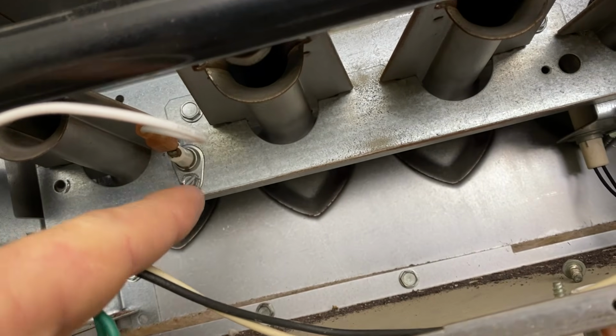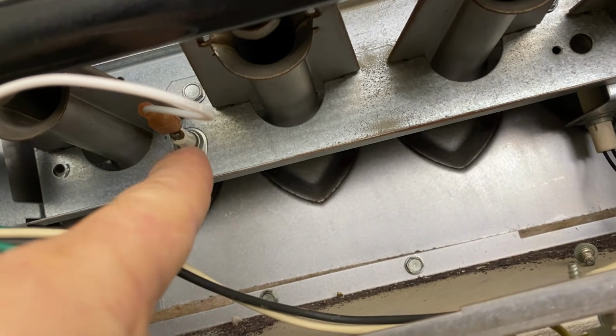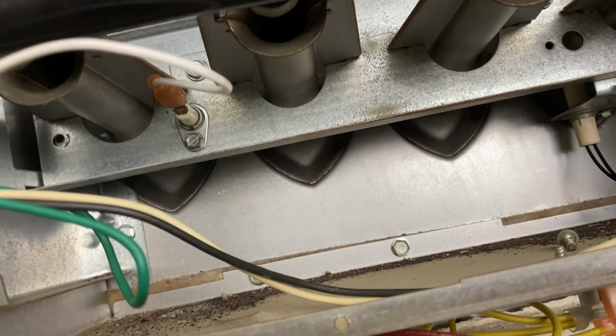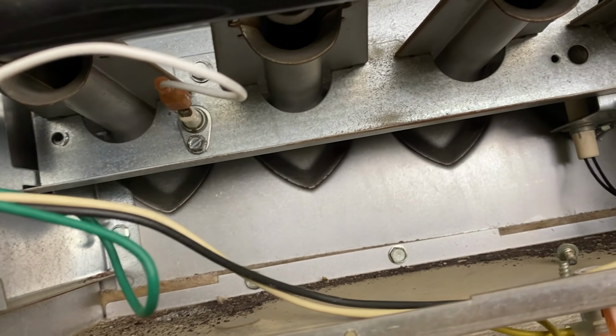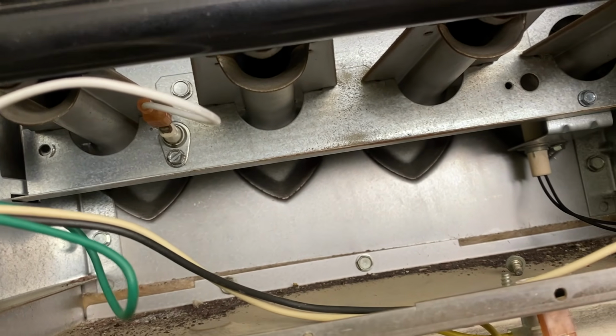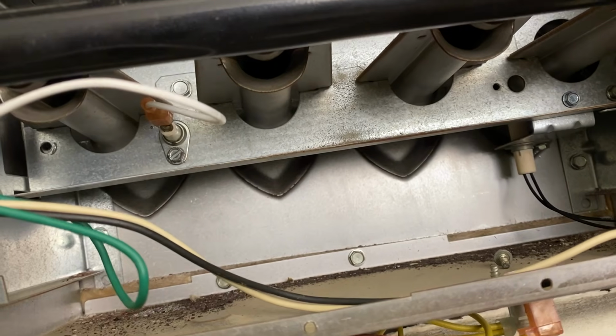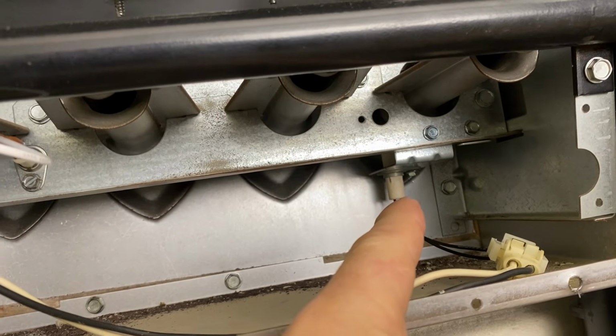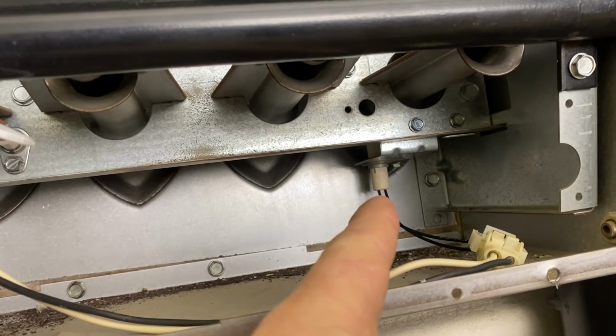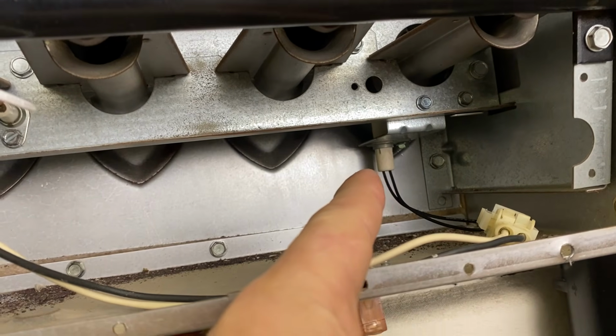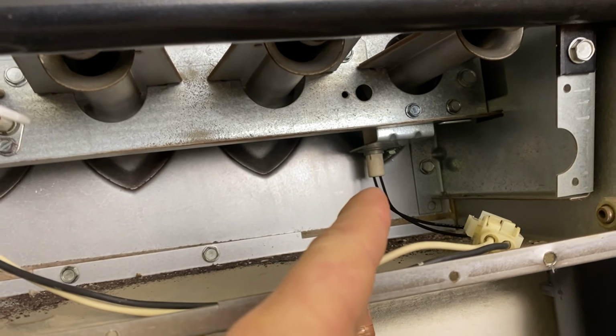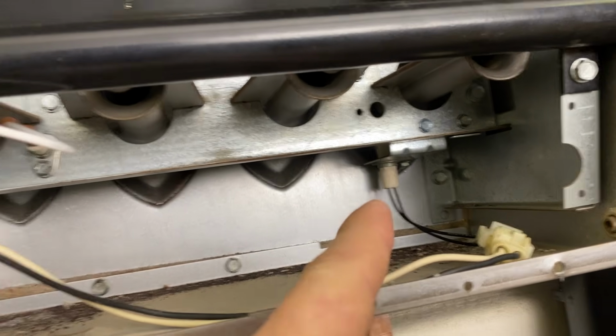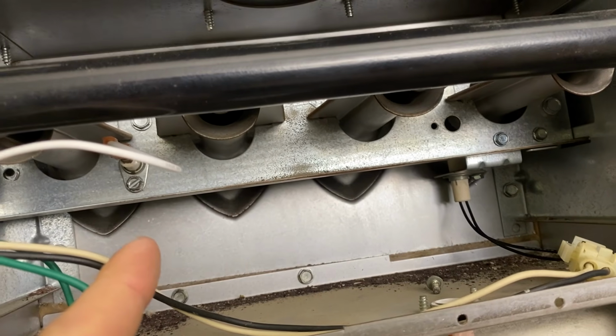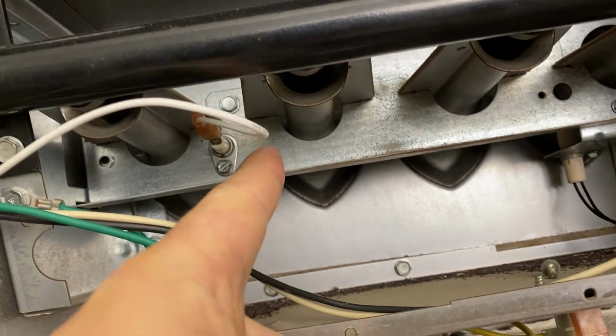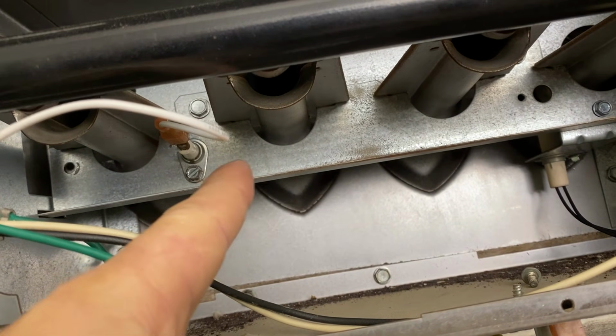That is a little piece of metal that sticks in front of one of those burners, and that senses a flame. If there's no flame, meaning if it didn't light, then after a few seconds it'll shut the gas off, so you're not just blowing gas in there. And so one thing you want to look for at this phase is the glow of that hot surface igniter. If you don't see any glow, then you have a bad hot surface igniter. If it does light, but after a few seconds it shuts off, then you have a bad flame sensor most likely. And so that is another cheap part that can be replaced.